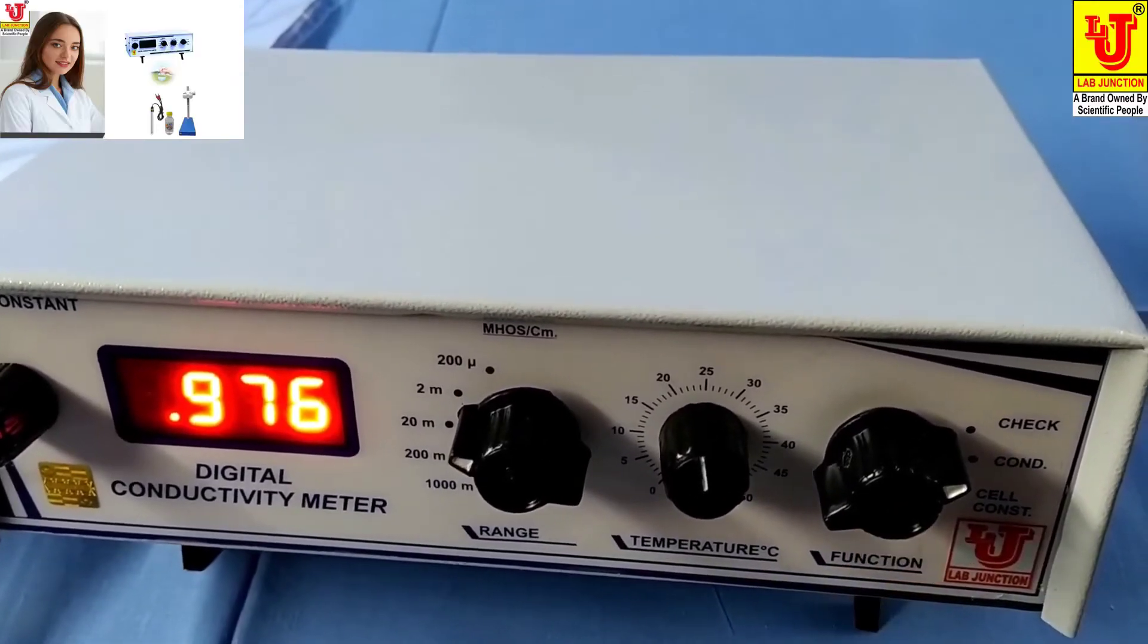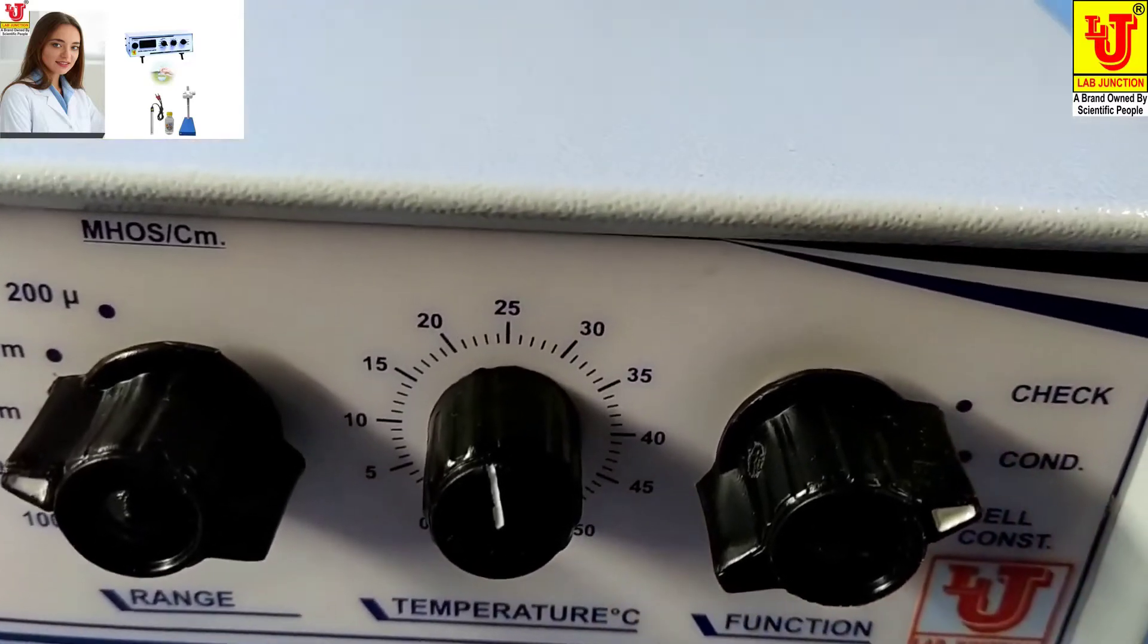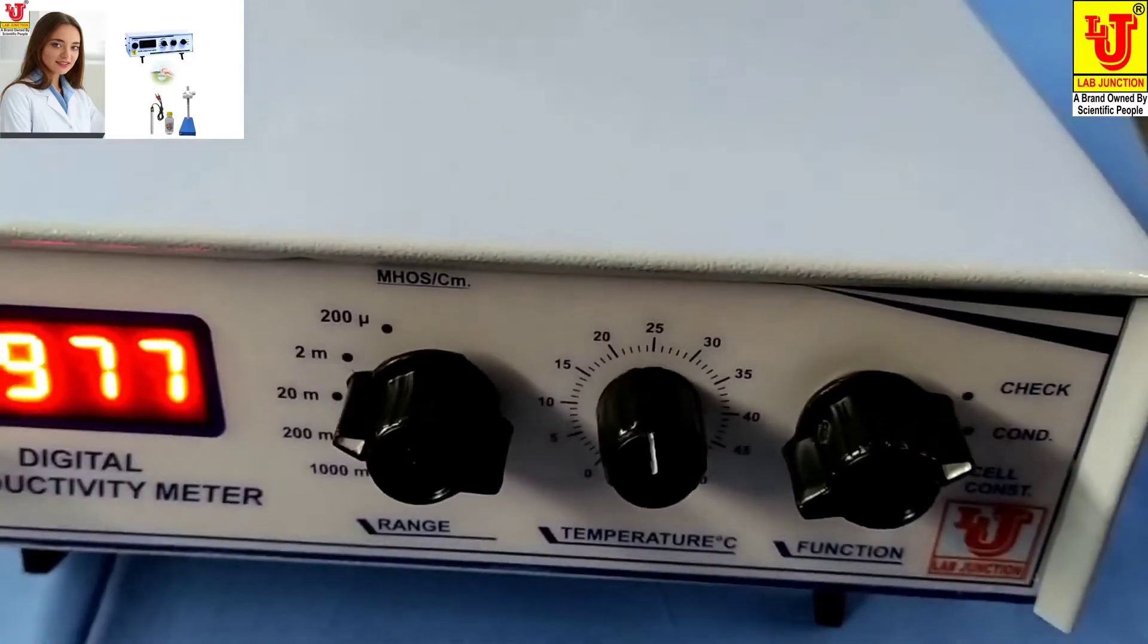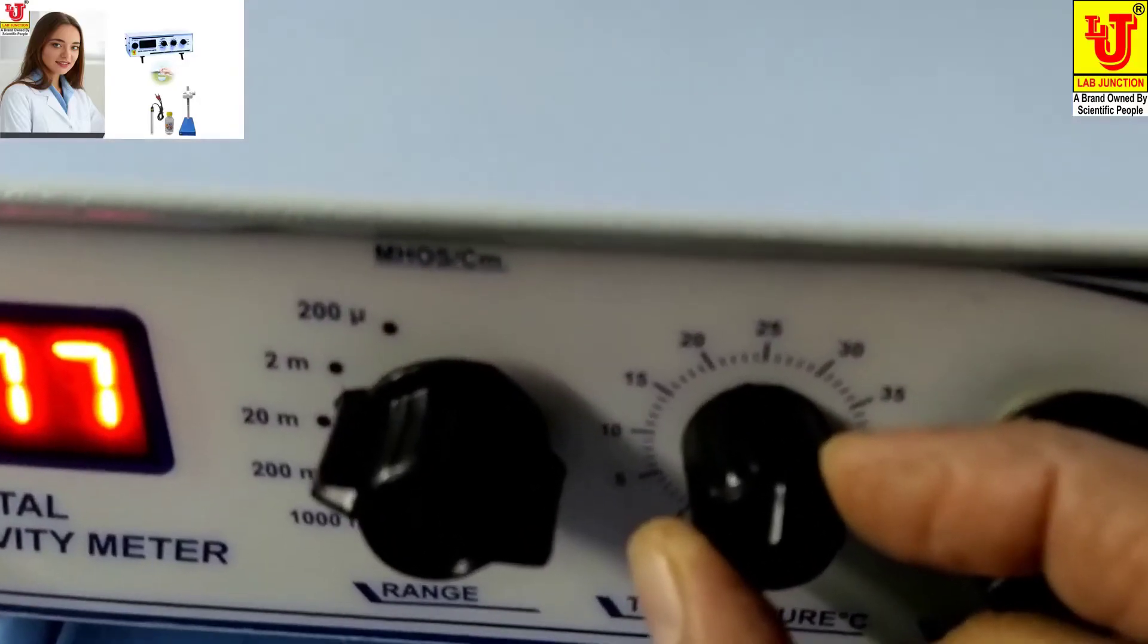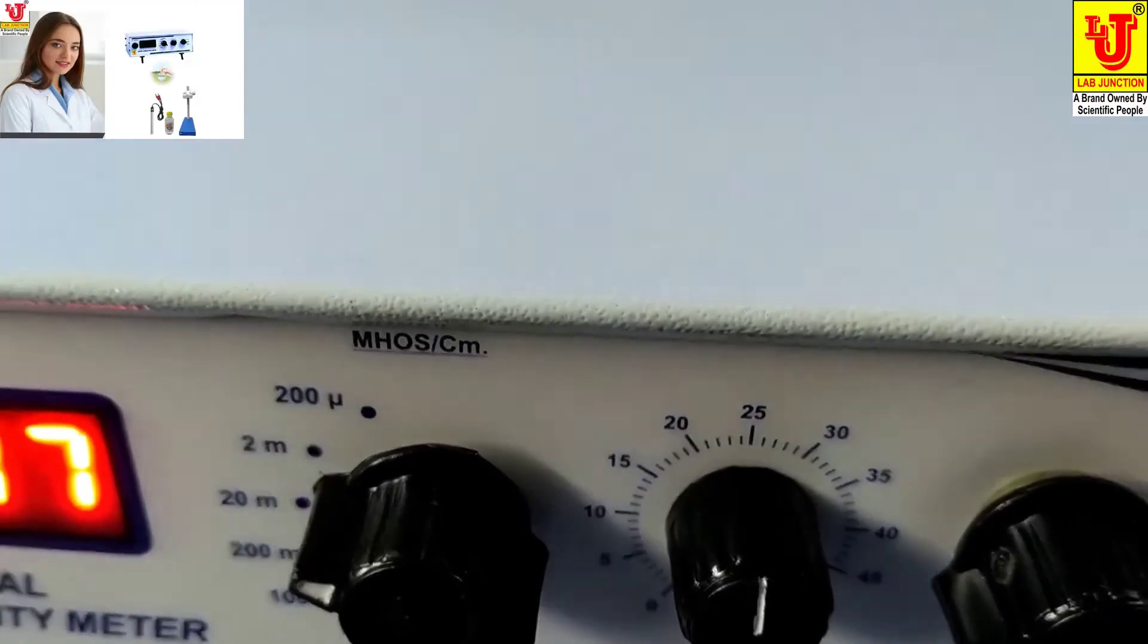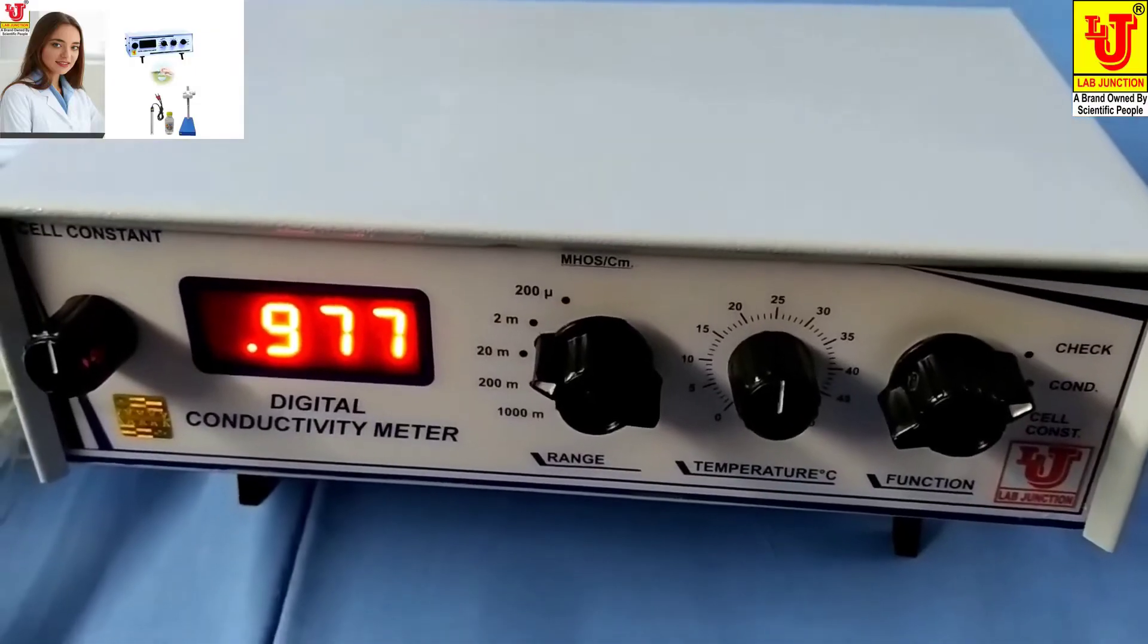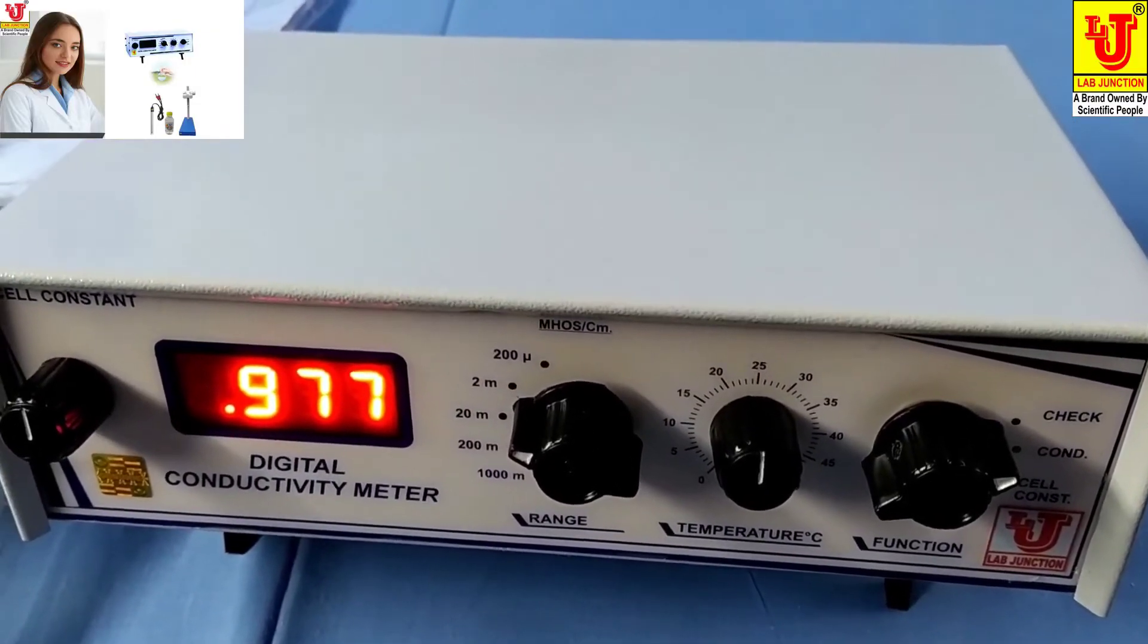In the function control, there are three positions: check, conductivity, and cell constant. First of all, you have to set temperature to 25 degrees. If you have a different temperature, then you can set it to your desired temperature.